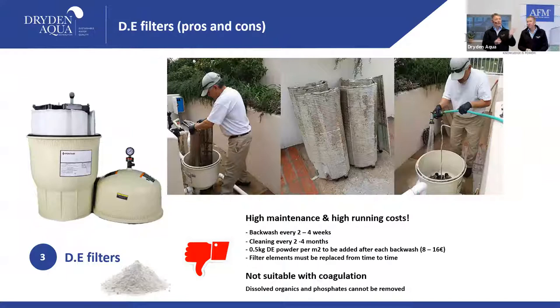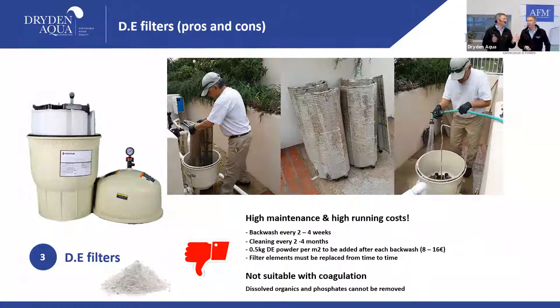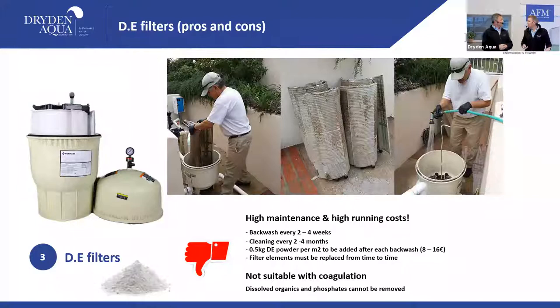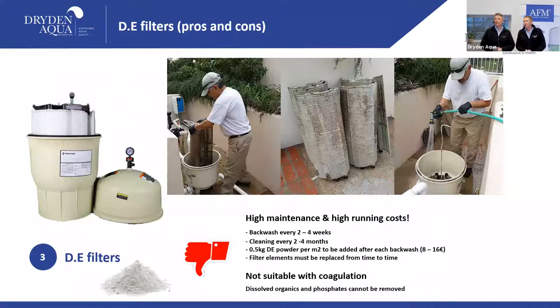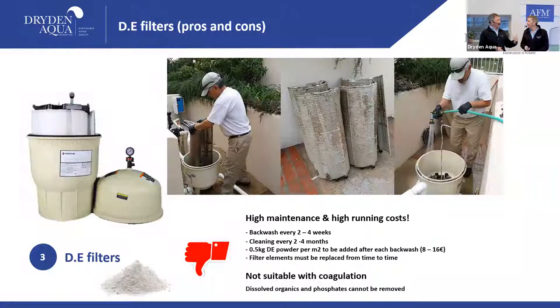DE filters should run at three to six meters per hour — around five on average. For a 10 m³/hr turnover rate you'd need one to two kilograms of DE every two to four weeks, each time pressure increases by 0.2–0.3 bar. There's an ongoing cost and you're handling powder that's not healthy to inhale. After a year or two, the maintenance burden and associated costs diminish the initial excitement.